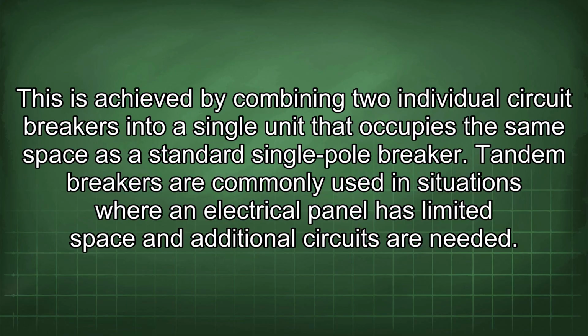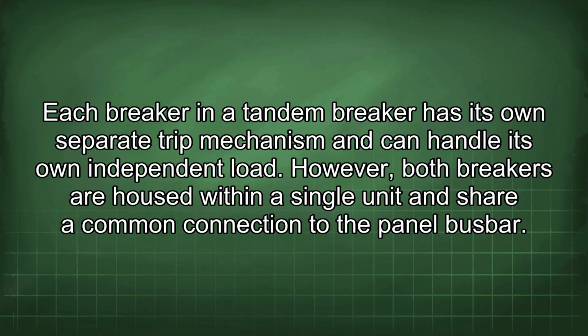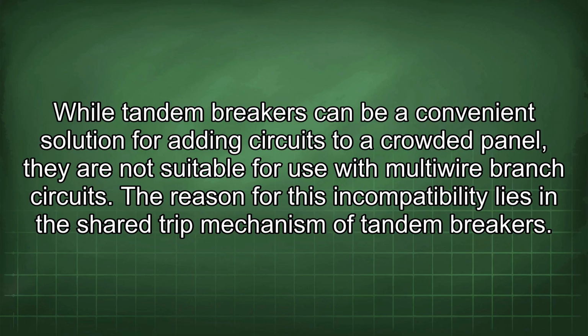standard single-pole breaker. Tandem breakers are commonly used in situations where an electrical panel has limited space and additional circuits are needed. Each breaker in a tandem breaker has its own separate trip mechanism and can handle its own independent load. However, both breakers are housed within a single unit and share a common connection to the panel busbar. While tandem breakers can be a convenient solution for adding circuits to a crowded panel, they are not suitable for use with multi-wire branch circuits.